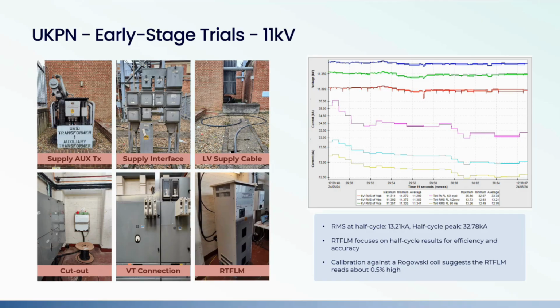In this particular example, this is a 132 to 11 kV grid site. It ultimately stood out because it ticked a lot of boxes, mainly the availability of space where we can install the unit, the minimal civil work and connection required, and most importantly, there's an on-site office which allowed our operations team to monitor the system closely. From a supply perspective, the LV supply was fed to the RTFLM via the auxiliary transformer that you can see in the top left-hand corner, via the LVAC board.